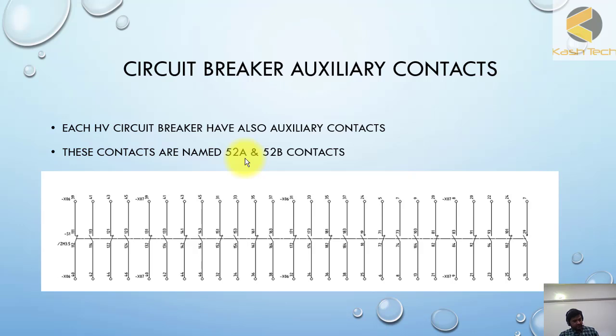We have already studied auxiliary contacts in part one. Each circuit breaker has its own auxiliary contacts; for the circuit breaker specifically we call them 52a and 52b — 52 is the code for a circuit breaker. 'a' and 'b' are two contacts: 'a' is the normally open contact and 'b' is the normally closed contact.